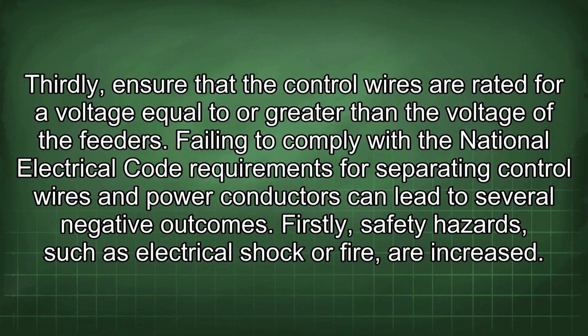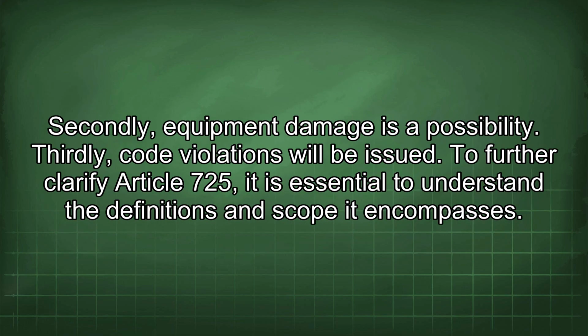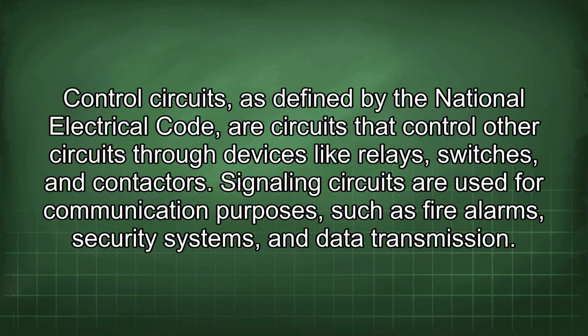Failing to comply with the National Electrical Code requirements for separating control wires and power conductors can lead to several negative outcomes. Firstly, safety hazards such as electrical shock or fire are increased. Secondly, equipment damage is a possibility. Thirdly, code violations will be issued. To further clarify Article 725, it is essential to understand the definitions and scope it encompasses. Control circuits, as defined by the National Electrical Code, are circuits that control other circuits through devices like relays, switches, and contactors. Signaling circuits are used for communication purposes, such as fire alarms, security systems, and data transmission.